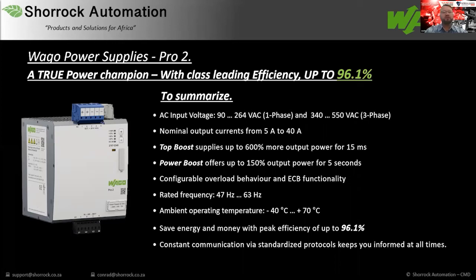Let's summarize. So, a true power champion with class-leading efficiency of up to 96.1% at full load on the 40 amp power supply. The AC input voltage can be between 90 and 264 volts AC, which is quite diverse, and also 340 to 550 volt AC on three-phase applications. We offer nominal output currents from 5 amps to 40 amps, top boost that can supply up to 600% or more of the power for 15 milliseconds, and power boost 150% of the output power for 5 seconds. It also offers a configurable overload behavior for electronic circuit breaker functionality. The rated frequency is between 47 and 63 Hertz, and the ambient operating temperature, I need to highlight that, not storage temperature, ambient operating temperature between -40 and +70 degrees Celsius.